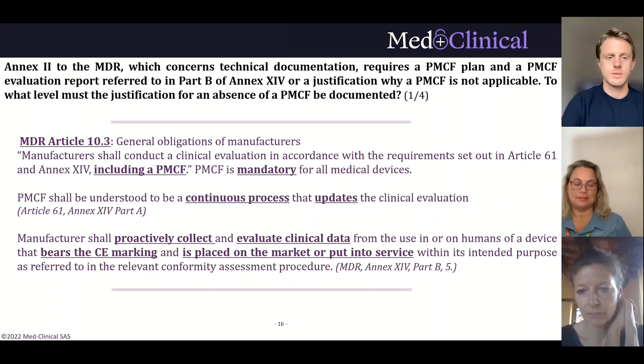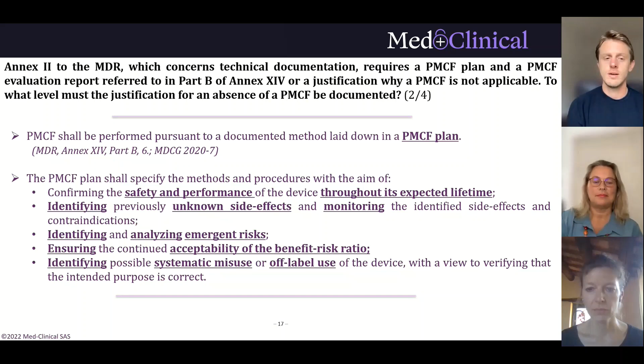First you start with the PMCF plan. The PMCF plan shall specify methods and procedures with different aims. The first aim is to confirm the safety and performance of the device throughout its whole expected lifetime. Next, you have to identify previously unknown side effects, monitor them, and also look out for contraindications. Then identify and analyze emerging risks, and ensure continued acceptability of the benefit-risk ratio. The last point is to identify possible systematic misuse or off-label use, which is quite common in daily practice for devices.